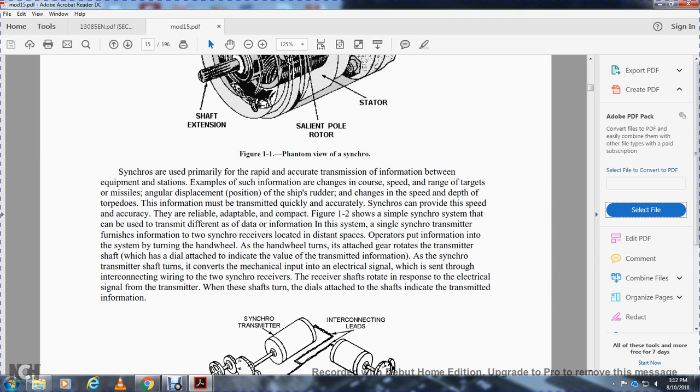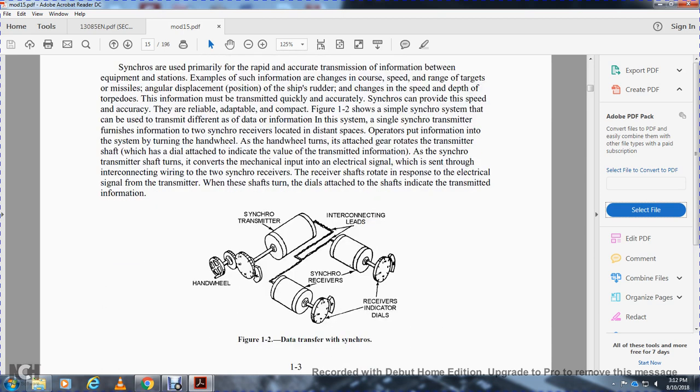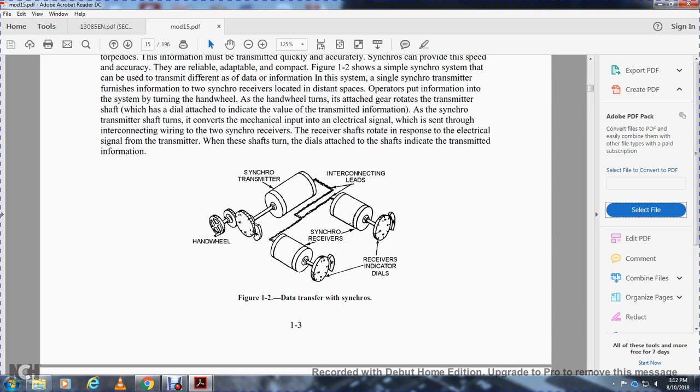The turning of the hand wheel rotates the attached gear and rotates the transmitter shaft, which is indicated on the dial showing the value being transmitted. The synchro transmitter shaft turns, converting the mechanical input to an electrical signal which passes through the interconnecting wires to the synchro receiver. The receiver shaft rotates in response to the electrical signal from the transmitter, and the dial turns to indicate the transmitted information.